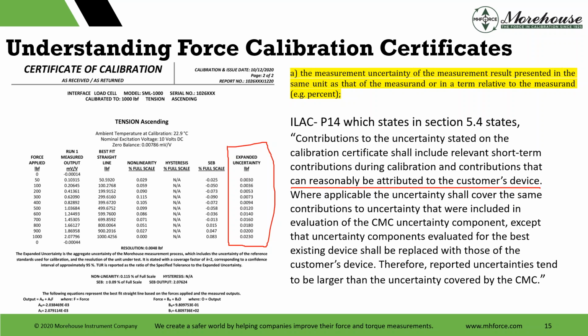The resolution is something that can change on various instruments submitted for calibration, and is something that we consider a short-term contributor. And then it says, where applicable, the uncertainty shall cover the same contributions to the uncertainty that were included in the evaluation of the CMC uncertainty component, except that the uncertainty components evaluated for the best existing device shall be replaced with those of the customer's device. Therefore, reported uncertainties tend to be larger than the uncertainty covered by the CMC.